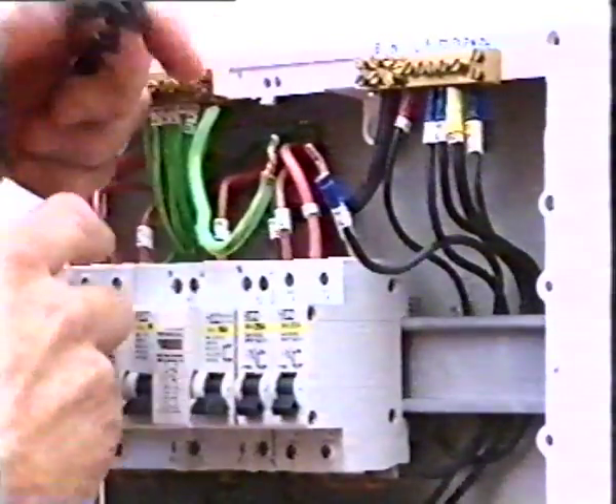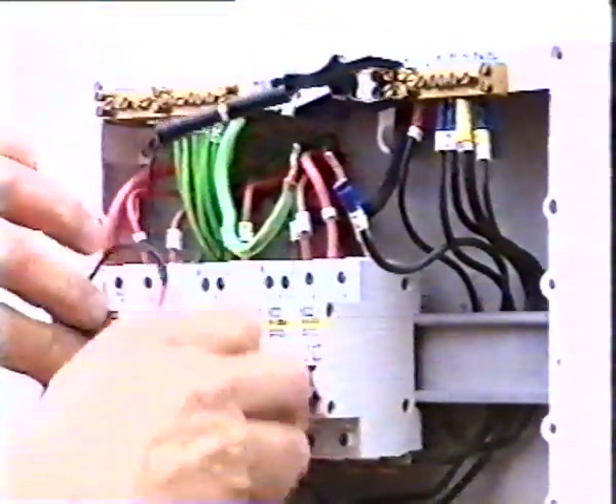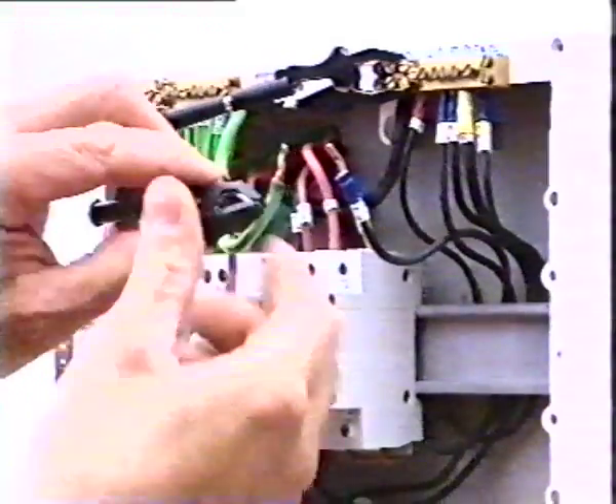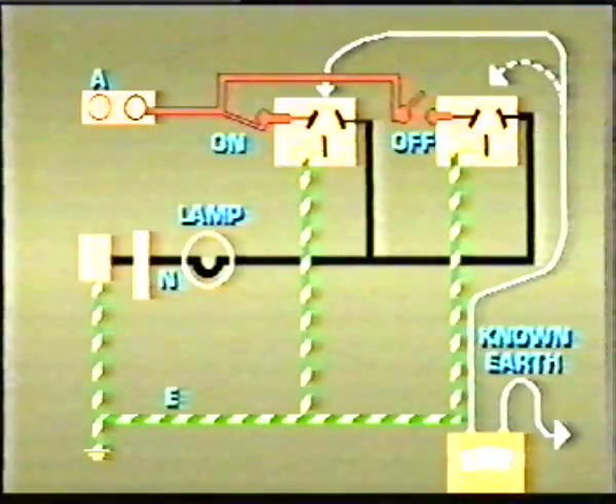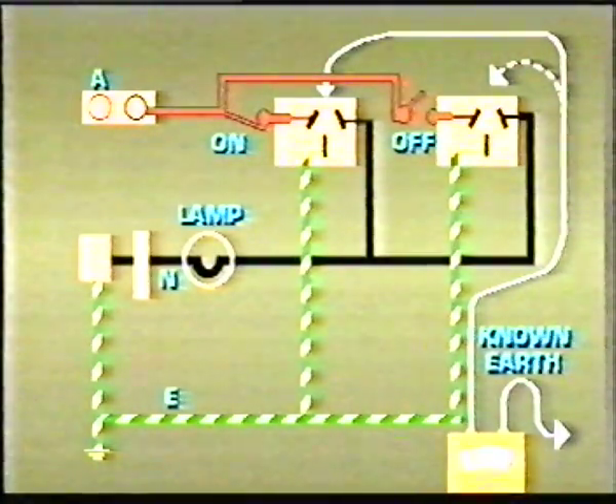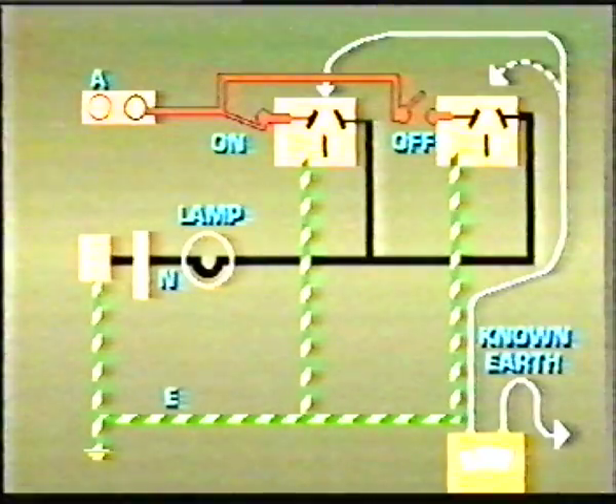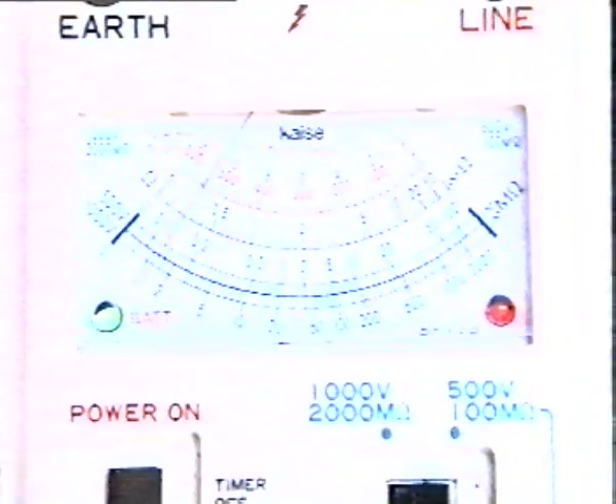To test the circuits comprising socket outlets, the neutral conductor of the final sub-circuit being tested is disconnected from the neutral link, and a 60-watt lamp is connected between the conductor and the neutral link. With one lead of the ohm meter connected to a known earth, the other lead is connected in turn to the neutral and earth contacts of the outlet. Correct neutral earth connection is proved when the neutral to earth indicates lamp resistance and earth to earth indicates a short circuit. Of course, circuits consisting of unlamped lamp holders can also be tested by this method.